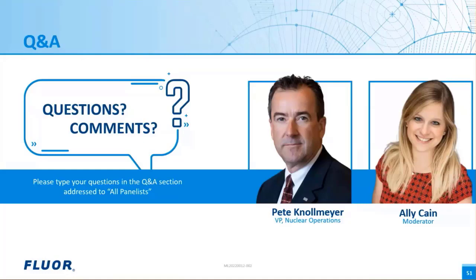Great, thank you. Next question, how is the quality of the cooling water for reactors maintained? So remember, there's two loops of water. There's the primary loop inside the reactor, which never goes outside the reactor vessel. And then there's the secondary water that goes through the steam generator. So the reactor water, there is a chemical addition and makeup system that penetrates the top end of the reactor, where you can add and change the chemistry of the reactor coolant. So that is one of those 2-inch diameter pipes that I mentioned. For the steam generator, we keep very tight chemistry control on the secondary water, because good chemistry control on the steam generators helps steam generator life.